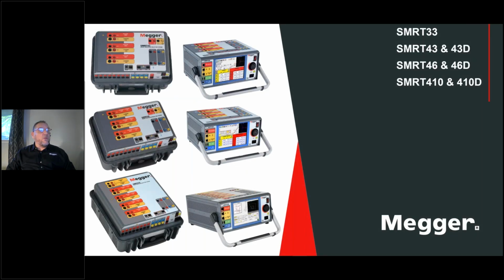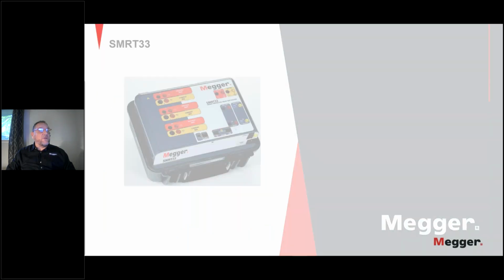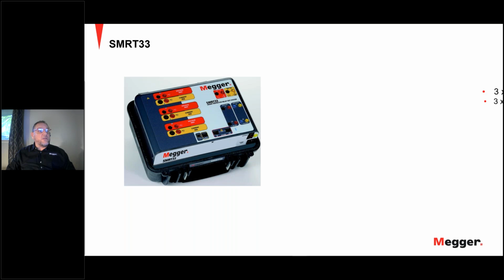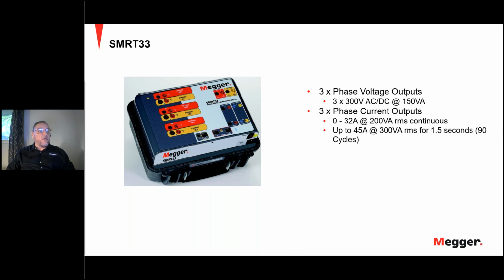Moving on, looking at the SMRT 33, 43, 46, and 410, as well as the D models. Firstly, I'm going to talk about the 33. The 33 is an entry-level 3-phase system, which still gives you 3-phase voltages and 3-phase currents, with a maximum output of 32 amps continuous, and 45 amps for 1.5 seconds. A note on this unit is that you can get up to 96 amps, 600 VA out of the unit if you combine the channels. Another note is that it does not have a system board in the unit, so you don't have the option of additional binary inputs and outputs, or a battery simulator for powering up the relays.